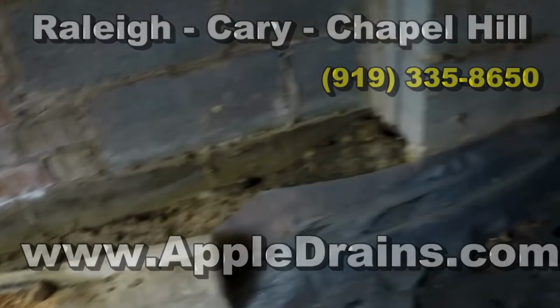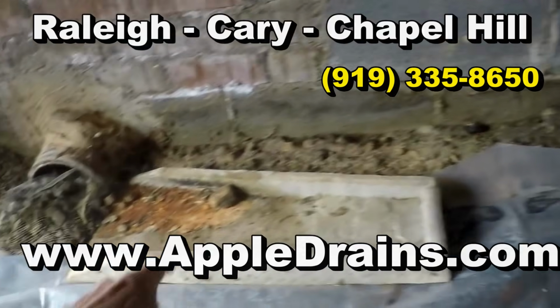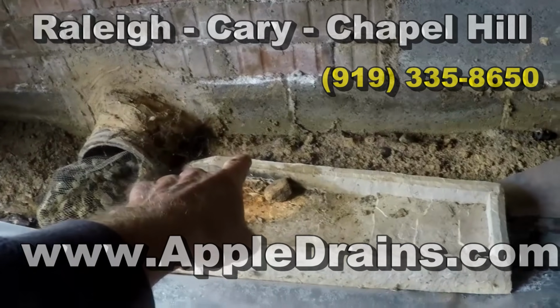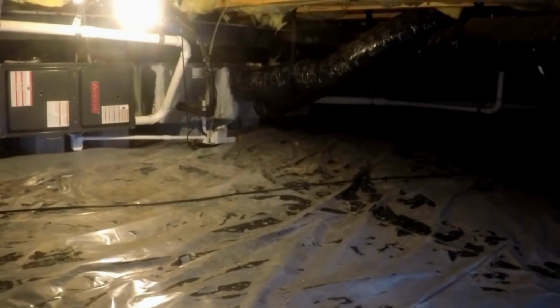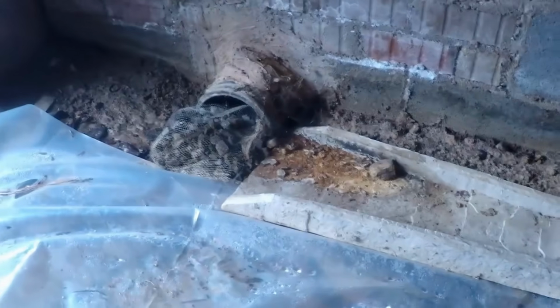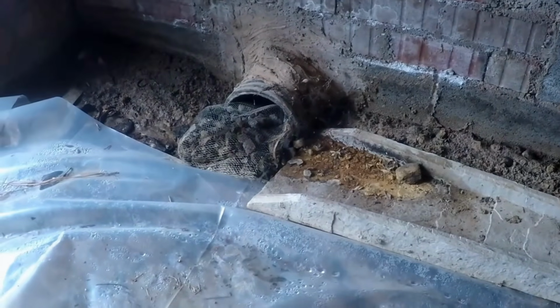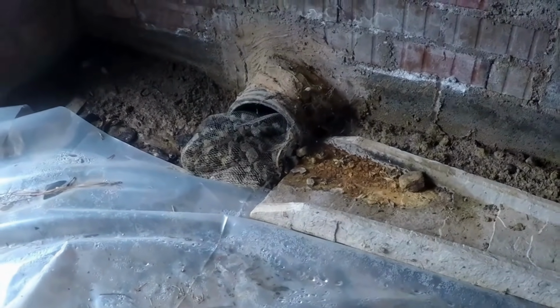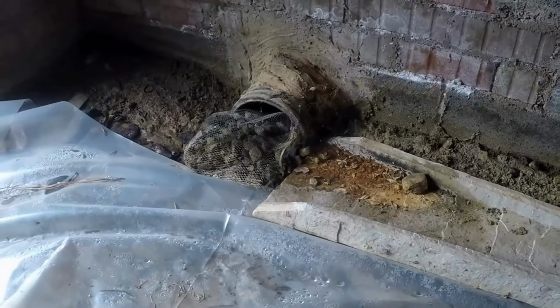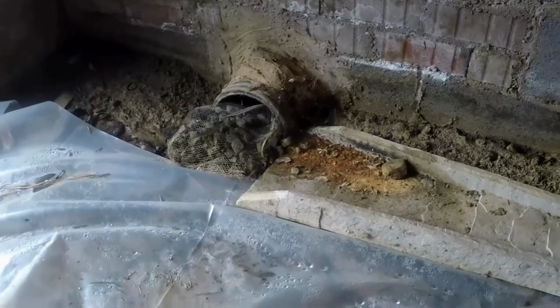If we take a look, you can see right away there's efflorescence here on the first course of block, and that tells you that there's water in the block, and you can see how wet it is. This crawl space is graded from the very front corner way back there. You can see the water comes down and it's supposed to drain right here. During an average rainfall, it works great, but again, when the groundwater fills up, there's no place for the water to go. What's needed here is a sump pump.